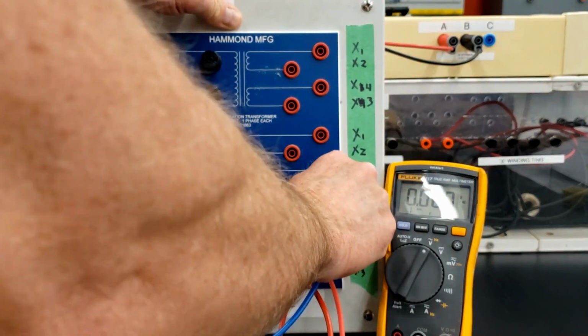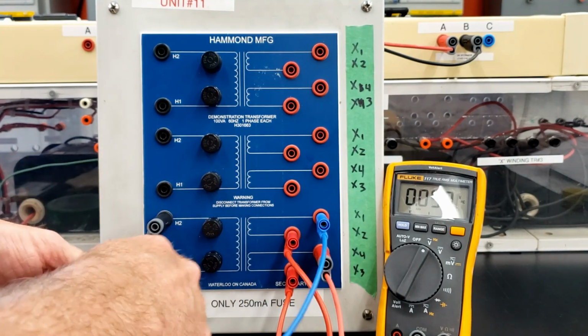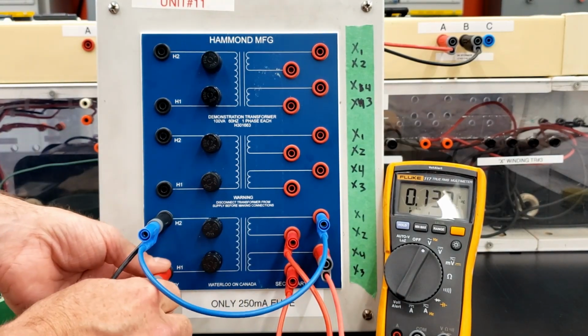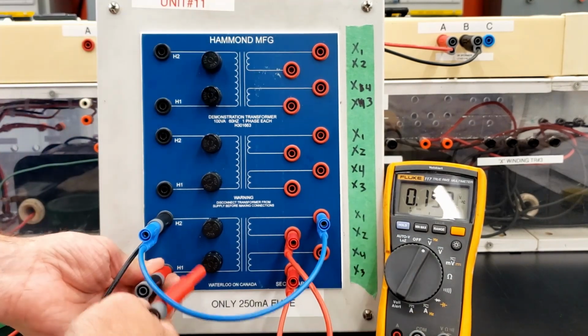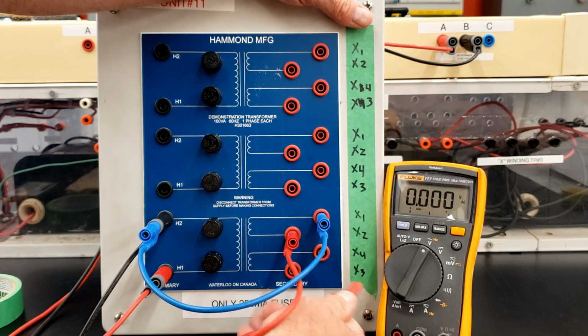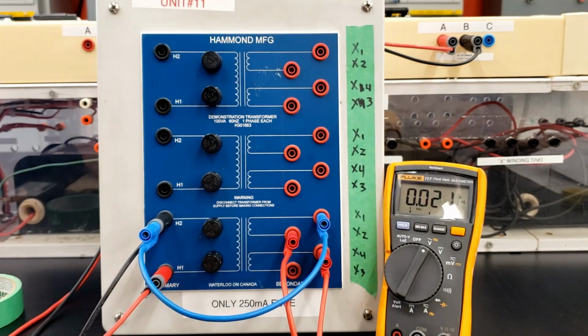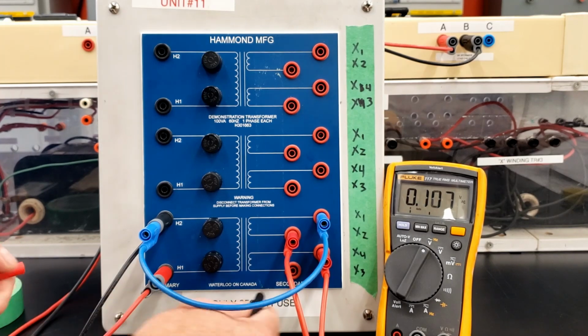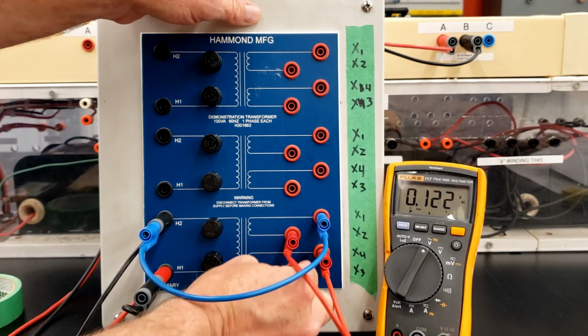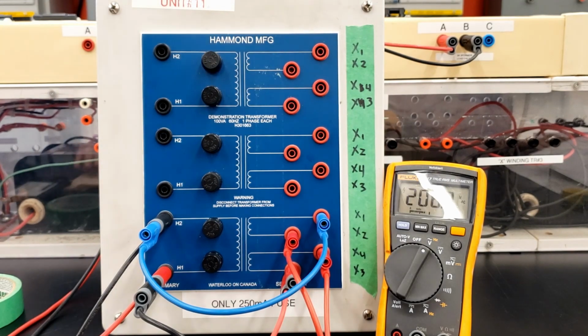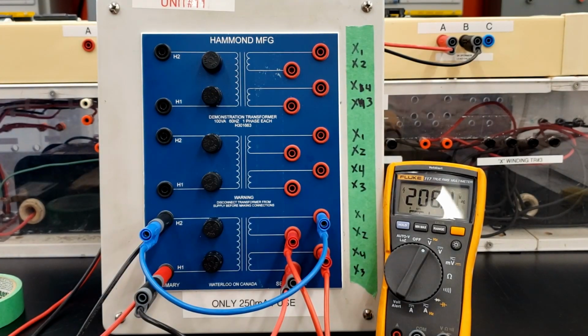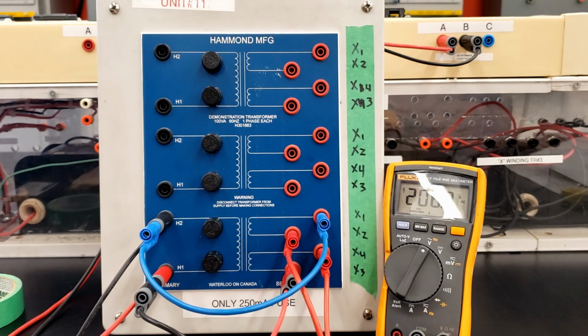But again, just one more time, I'm going to keep this one as the additive polarity here. And then I'm going to remove my meter for 2 seconds. And then last thing I'm going to do is show you that if I had connected to the wrong terminal here, then between the two open connections I should see 208 volts. There we go. Okay, so at any point if you see 208, then take one of the windings and scratch out the terminals and flip the polarity of that one winding. Okay, one of the windings is opposite from the other.